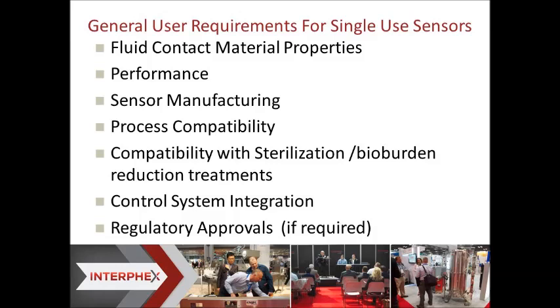Performance: you have to make sure the sensor meets your accuracy and repeatability specification. You want the sensor made in a clean manufacturing environment, because that will be introduced to your process. You want process compatibility with any fluids used in the process as well as any conditioning steps. You want compatibility with any sterilization and bioburden reduction treatments, and you may need control system integration and also regulatory approvals.